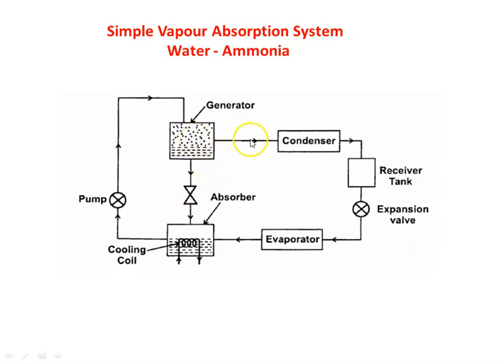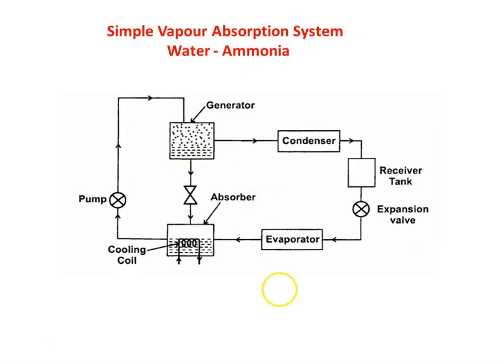The ammonia vapor goes to the condenser, is condensed, and converted into saturated liquid form of ammonia collected in the tank. It is then expanded in the expansion valve, the vapor absorbs heat in the evaporator, and the cycle repeats. So this is the vapor absorption refrigeration system, where the compressor is replaced by the absorber, generator, and pump.